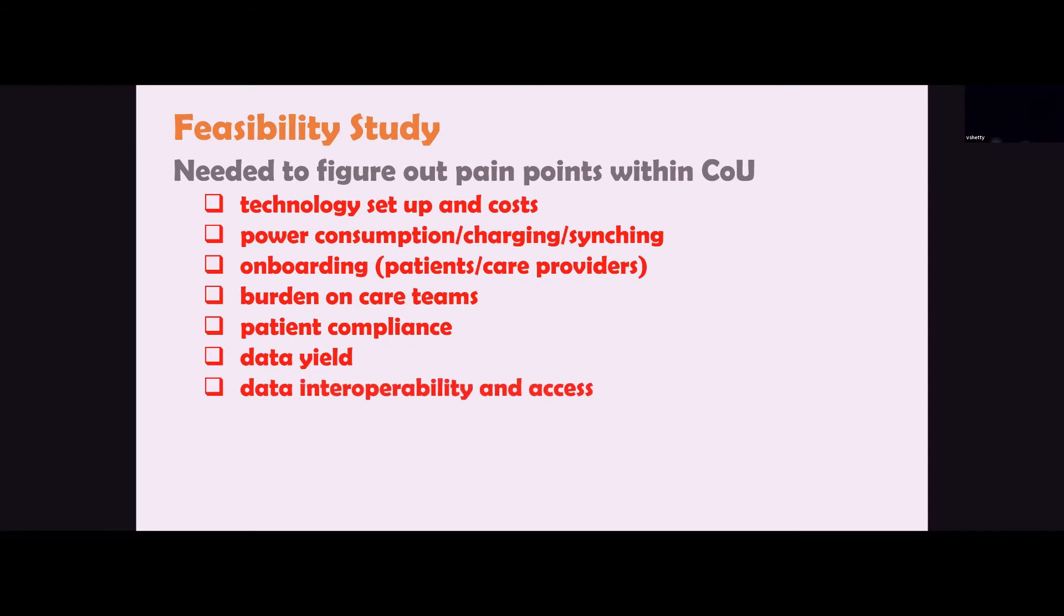Data interoperability can be a huge problem when you're dealing with devices with proprietary systems, which are by necessity closed systems. Also, when the current infrastructure in healthcare settings does not allow integration of sensor data with EMRs, those of you who interact with EPIC will know what I'm talking about. Your sensor data will not flow into EMR systems, so there is no opportunity for data storage and linking with clinical data or for further analysis during a patient care journey. So think about this upfront.